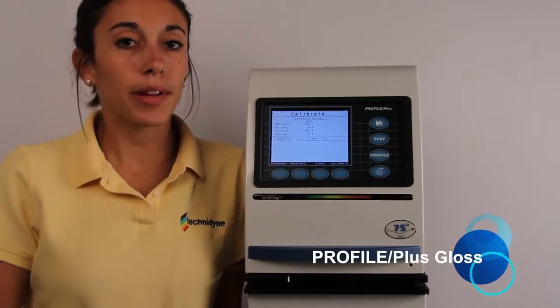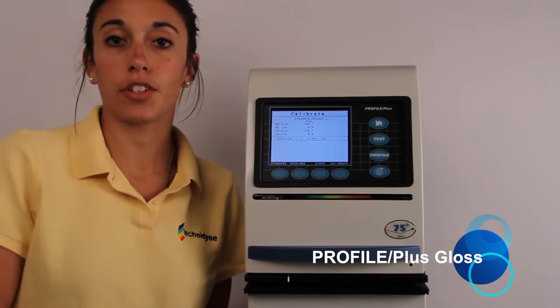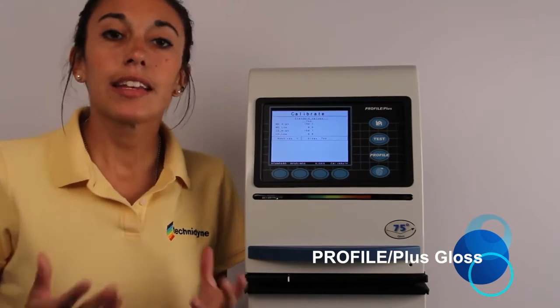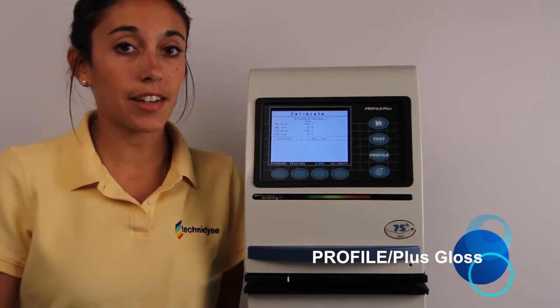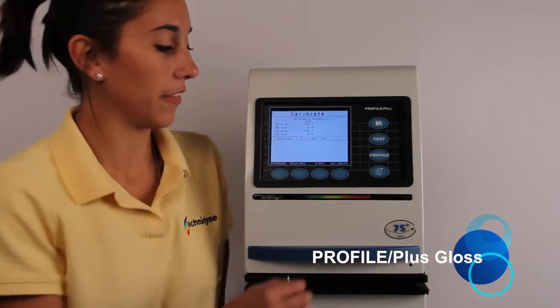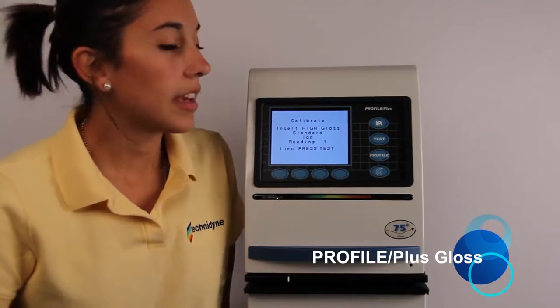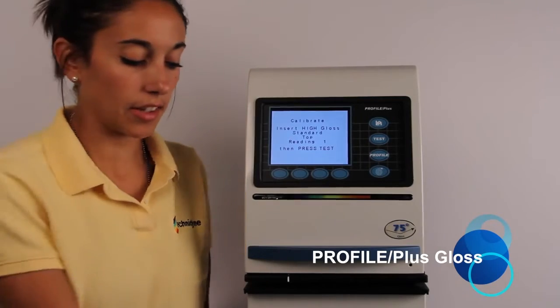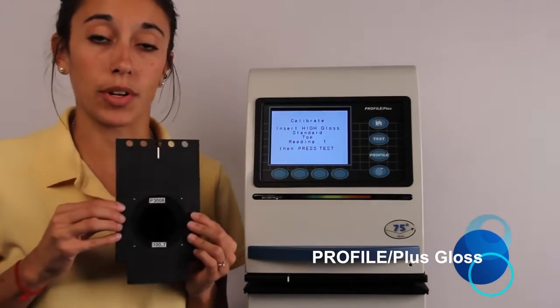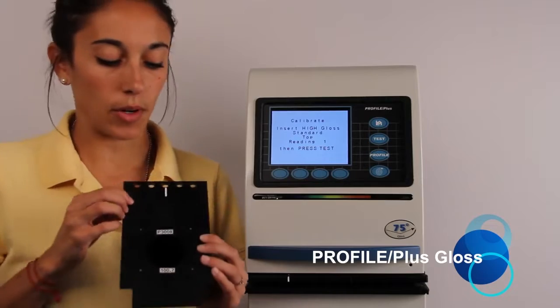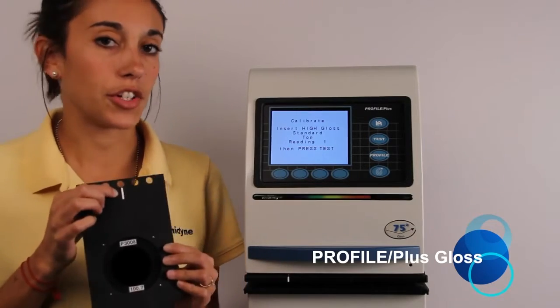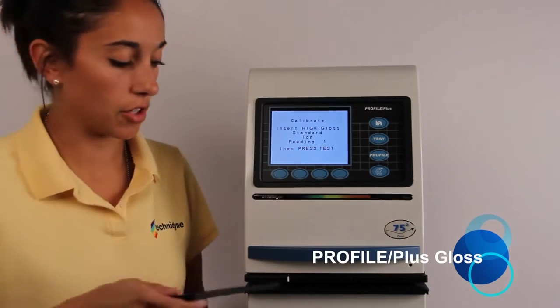Because this instrument was only manufactured to measure the top side, we won't be doing a two-sided calibration today. Now, once you have all your values assigned, we're going to go ahead and press the Calibrate soft key again. It's going to ask us to load our high gloss standard, which for us is our 100.7. An important thing to remember is to make sure that the white line on your standard matches up with the white line on your instrument.